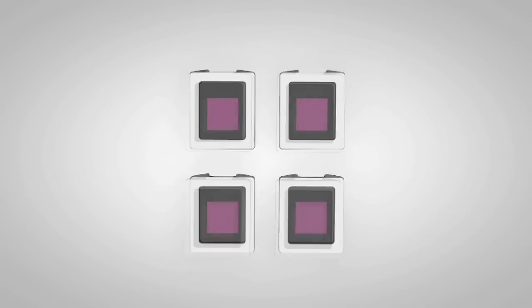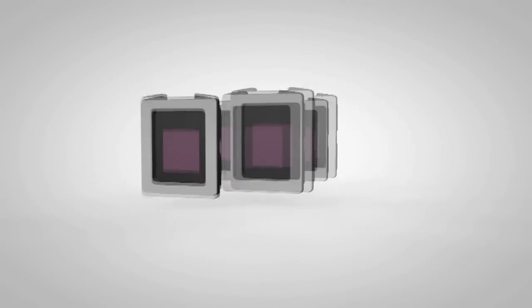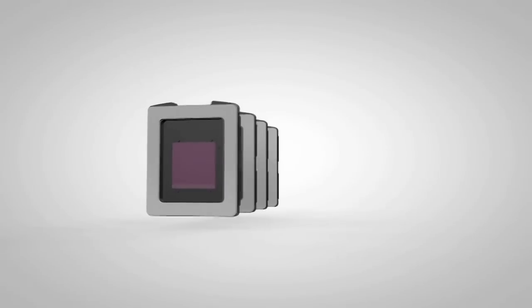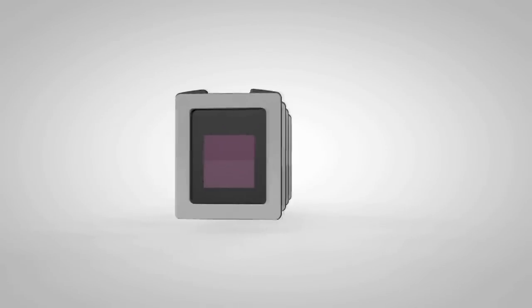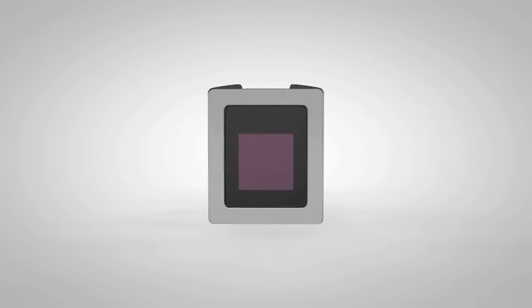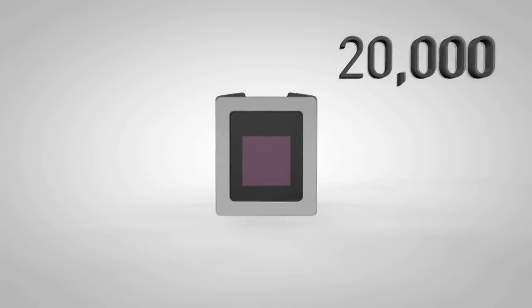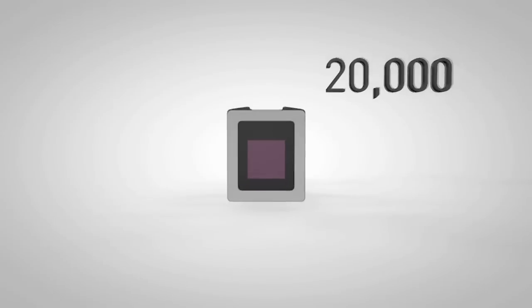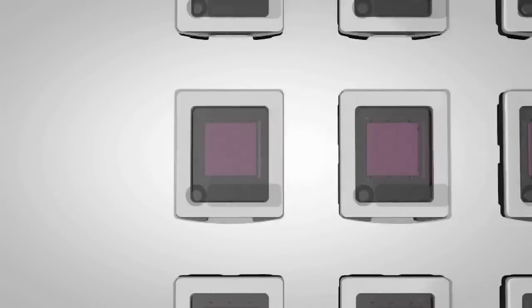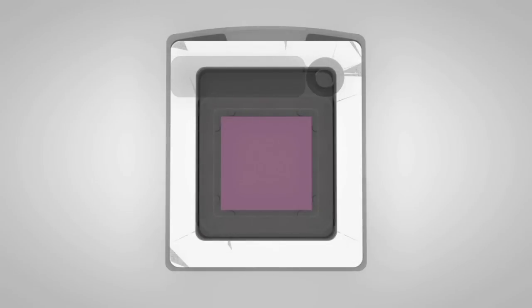The QuantStudio 3D chip offers 20,000 partitions that accommodate a single sample and two target measurements using both FAM and VIC labeled assays. Should you feel that your experiment would benefit from greater than 20,000 digital reactions, you can create a larger virtual chip through pooling together measurements from multiple chips. Even a million reactions is no problem as you simply configure the software to calculate everything for you.